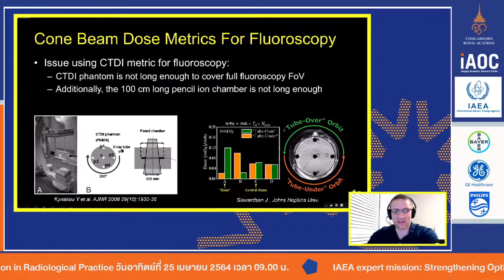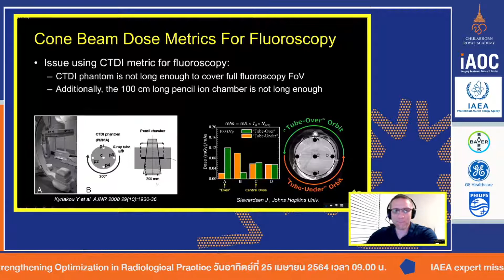Now I mentioned that a single CTDI phantom is not wide enough. So obviously we could stack 2, 3, or 4 of these phantoms together, right? Well, the problem is our ion chamber probe is only 100 millimeters. It's not 400 or 500 millimeters, which is really kind of what we need. All right, so how do we get past all of this? I'm going to give you 3 options. You can pick your favorite. I will tell you what I do at the end, and no spoiler alert, it's the easiest of the 3.